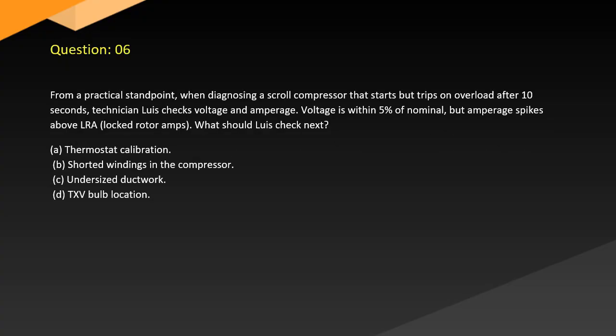Question 6. From a practical standpoint, when diagnosing a scroll compressor that starts but trips on overload after 10 seconds, technician Luis checks voltage and amperage. Voltage is within 5% of nominal, but amperage spikes above LRA, locked rotor amps. What should Luis check next? A. Thermostat calibration. B. Shorted windings in the compressor. C. Undersized ductwork. D. TXV bulb location.